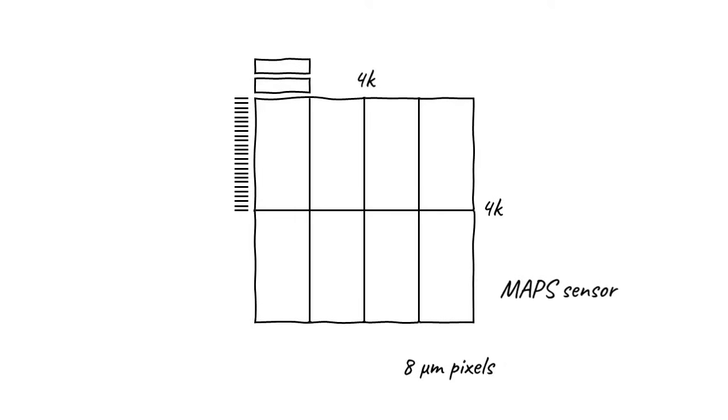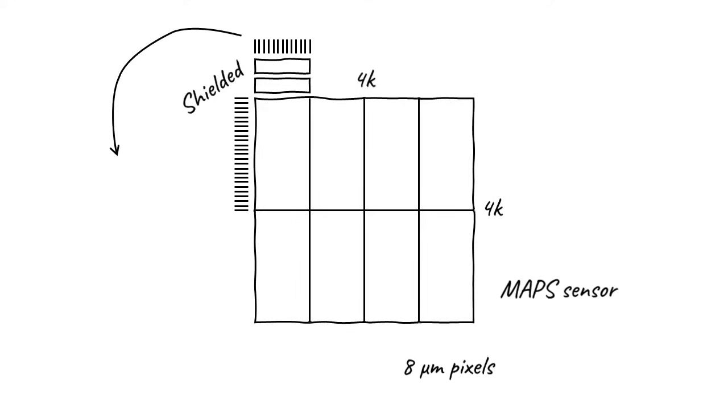First, while the complex circuitry in these blocks are part of the sensor, they are at the edges of the sensor so they can be effectively shielded from the electron beam. And second, these two blocks work together with the unique pixel architecture in the Apollo sensor to generate a completely digital output representing detected events on the sensor.